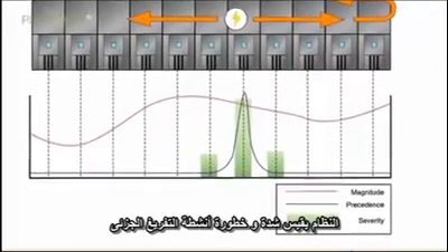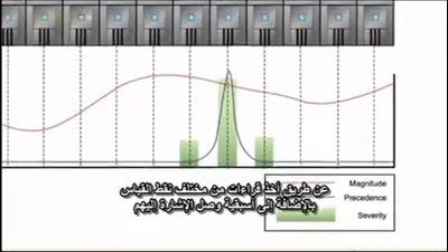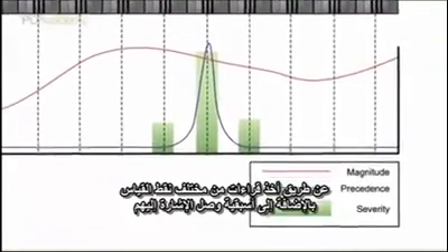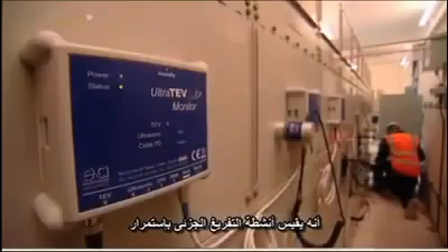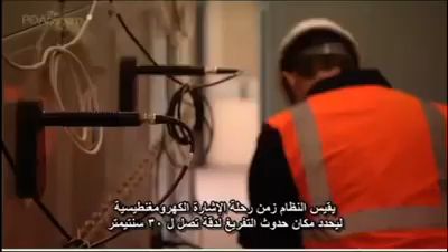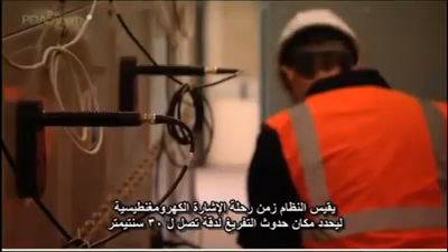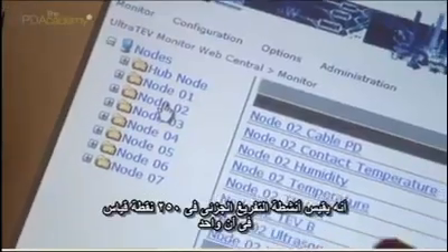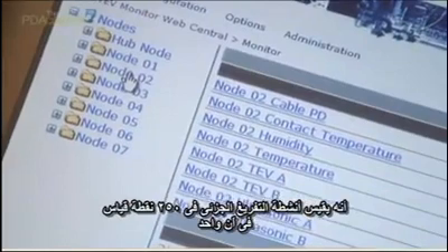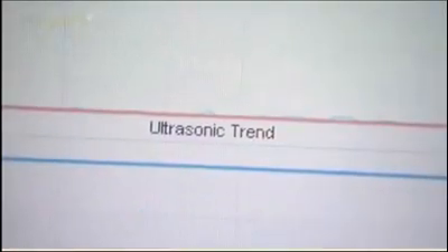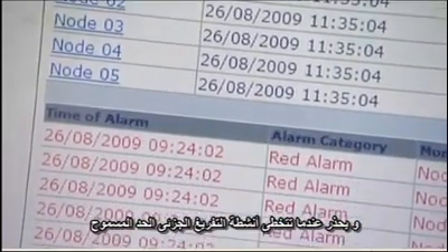The system measures the severity and magnitude of PD activity by taking readings from multiple measurement points, all with precedence between them. It continuously measures PD activity non-intrusively. It uses time-of-flight measurement to locate PD activity to within 30 centimeters. It measures PD activity at up to 250 points simultaneously. It records PD activity over time. It analyzes and reports PD activity, including tracking changes in PD activity over time and warning when activity exceeds specified parameters. And it automatically transmits alerts by text message or email when PD activity reaches a critical level on any asset being monitored for complete peace of mind.